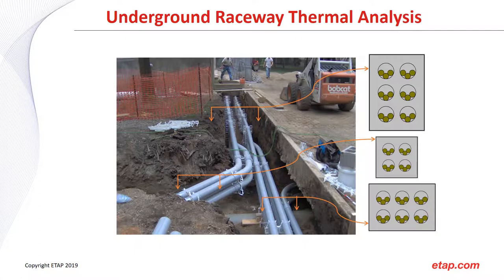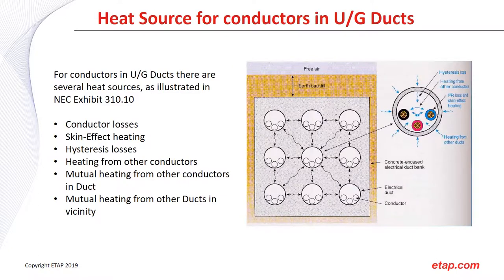Let's talk about underground raceway thermal analysis. A typical installation might be a 3×2 configuration — rows by columns. In any given installation you may have different configurations, either direct buried or in raceways. It's important to take into account the different cross sections to arrive at the most conservative calculation when doing sizing. For conductors in underground ducts, there are several heat sources.